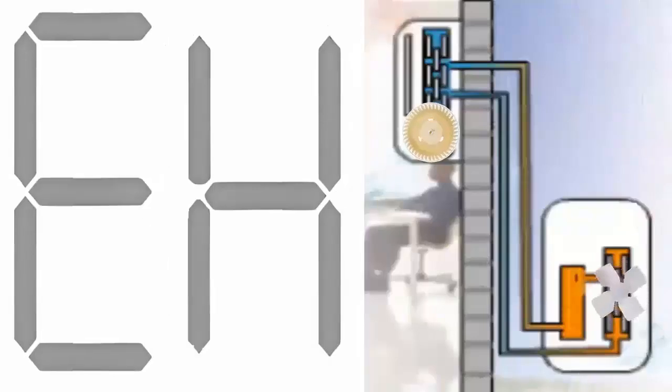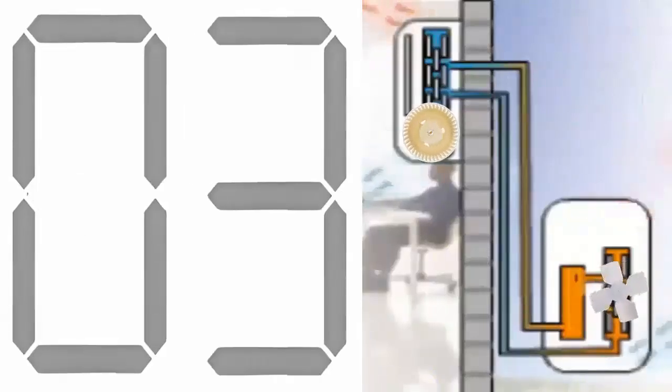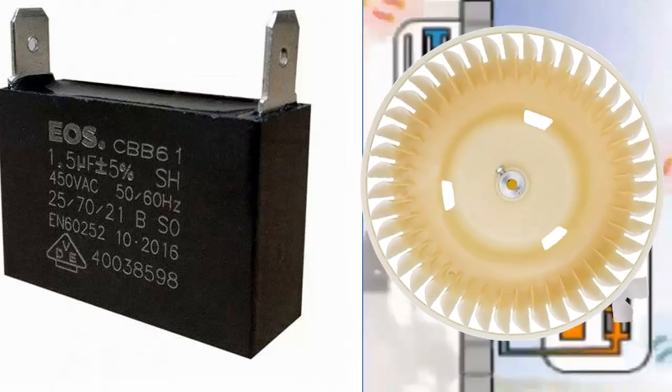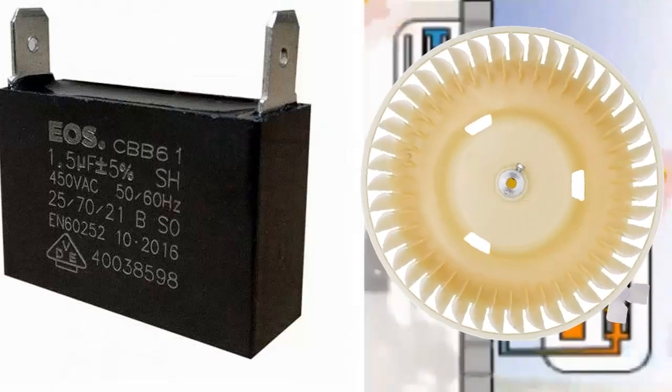4. If the airflow from the fan turbine is low, the fan motor capacitor might be defective. Replace the defective capacitor with a new one of the same capacitance.